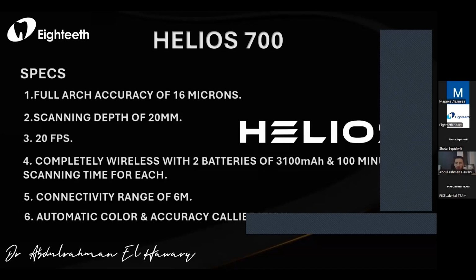And after personally using the Helios 700, I've found two very important things. Automatic calibration is something with the whole Helios series. Our scanners do not come with a calibration kit, so the whole hassle of calibrating your scanner is completely eliminated with the whole Helios series. And one of the most important things and the huge difference with the Helios is that we now have an optimal bite registration and bite recording.